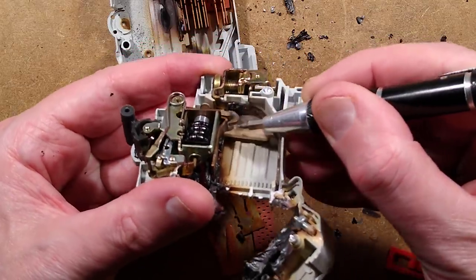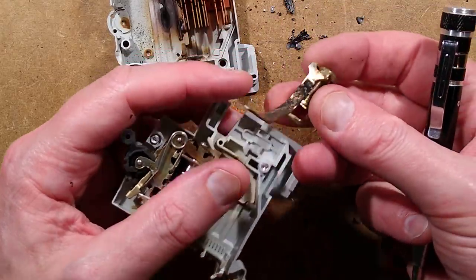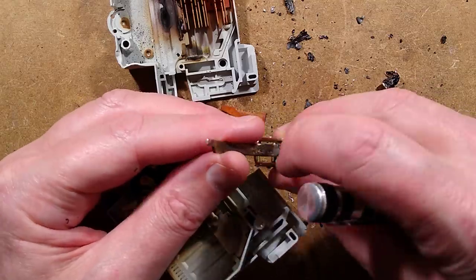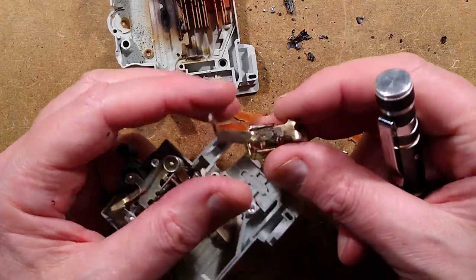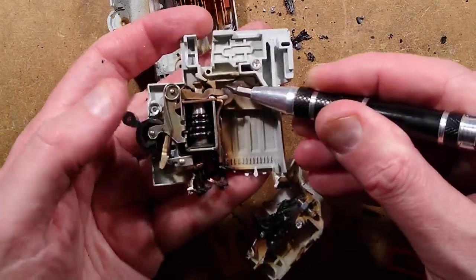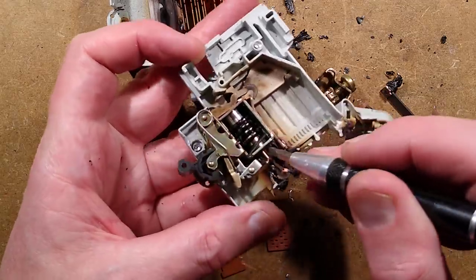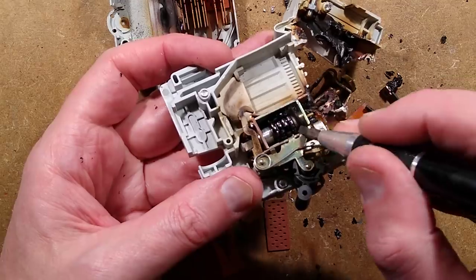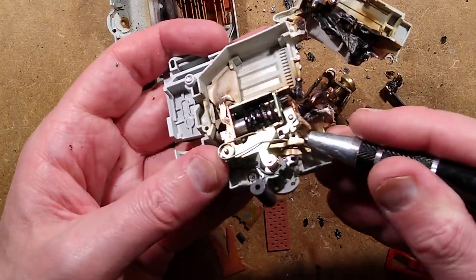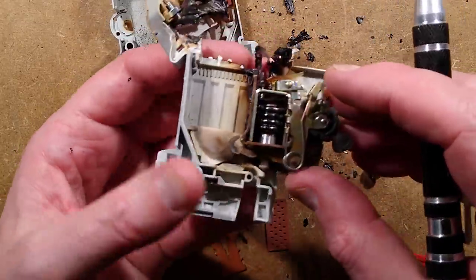There's the arc-quenching arrangement - it couldn't do much about this though. It's pretty much the full current path. The contacts there look relatively intact. Here's the arc chute guide - it is very sooty. I wonder if this has been closed repeatedly into a fault until it welded, and then the current just continued to flow. It's unusual to see this - the magnetic coil is black, all the lacquer on the windings has cracked. That shows a lot of current has flowed through it. Very impressive.